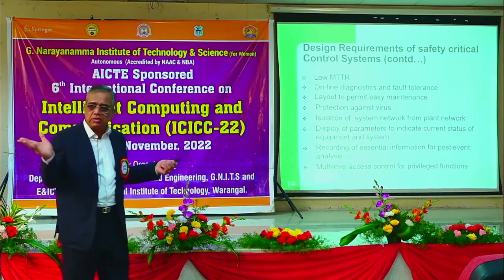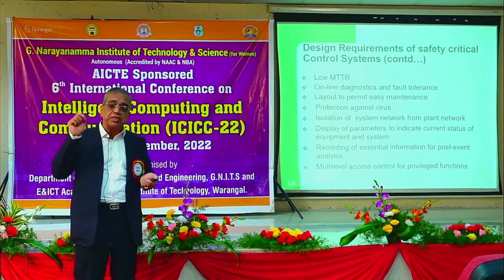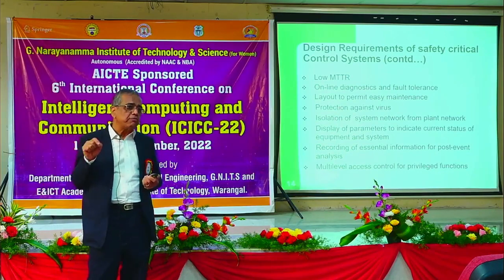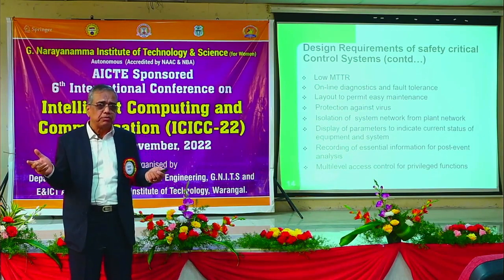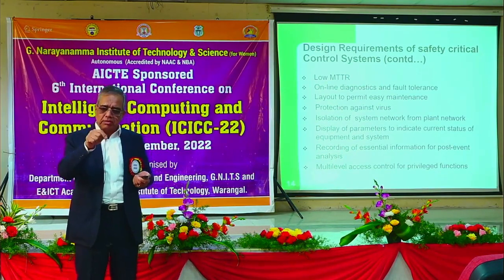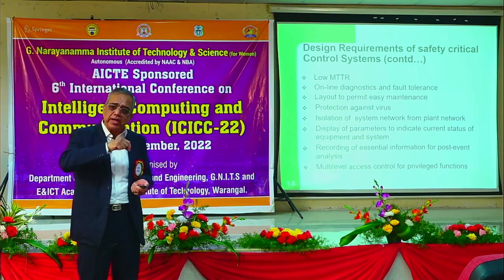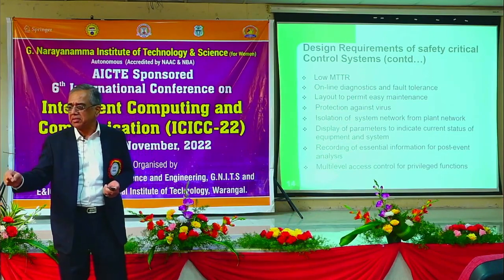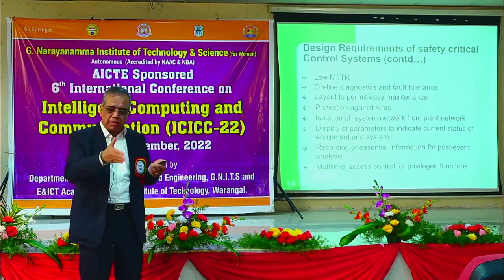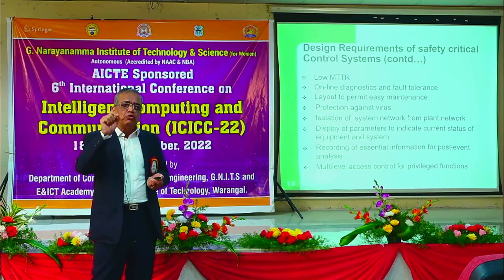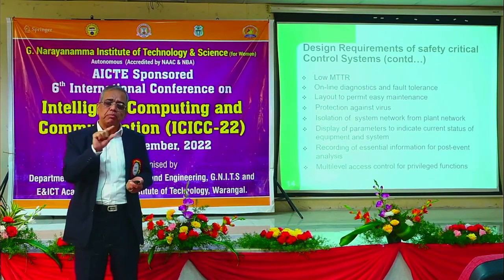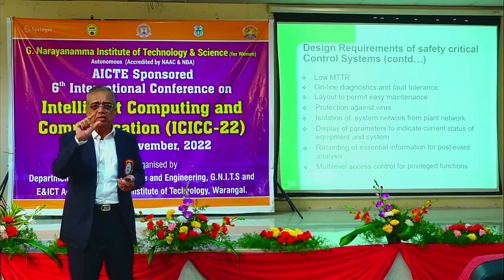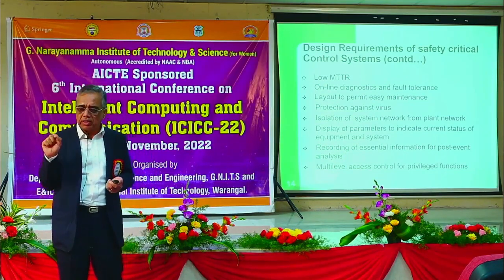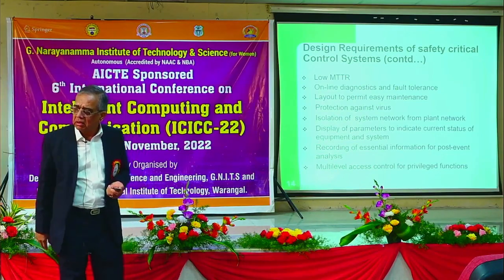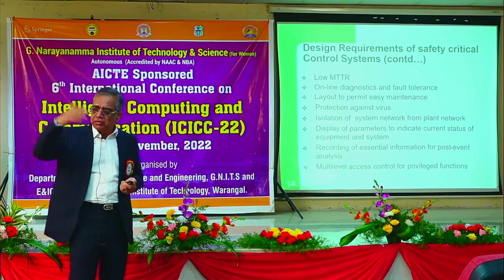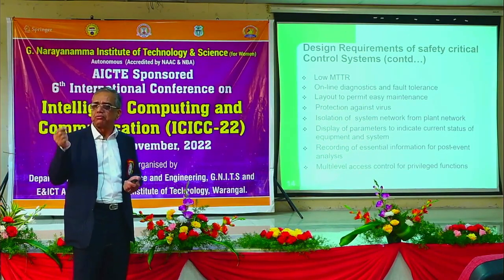Online diagnostic and fault tolerance. Fault tolerance means a triplicated system, a fault in one system does not affect the others. But what is online diagnostics? We design our own hardware, and each hardware is designed for its online diagnostics. For example, digital input: let us say normally it is 1 or open. You will, through software, do a finite impulse testing to force it to close and see whether it is reading properly or not. Similarly, for analog input, you have multiplexers, you have a number of inputs, and then you test whether it is giving the correct output by giving one to ground and another to reference input. There are reference ICs available, giving a very precise voltage. So that will show it is linear and to scale. Like that, analog output you feed back and read it, digital output is a relay output, so you see the energization of the coil, etc.